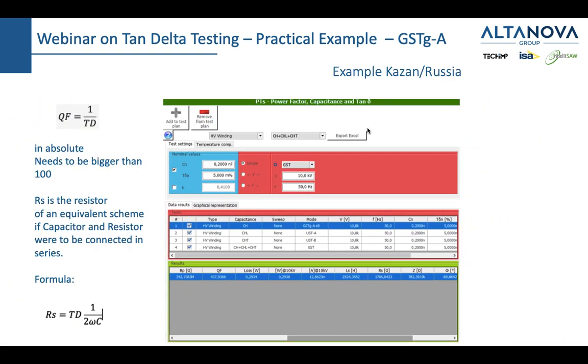The next would be, if 12 kV is the voltage with which the test is done because the insulation is polarized, is there any chance to perform the test on a low voltage side? On a low voltage side, in transformers where the secondary side is less than 10 kV. So, well, when I say 12 kV, I'm saying 12 kV on a transformer which has a nominal voltage more than 12. Of course, if you have 10 kilovolts, you will do a test at 10 kilovolts. And actually, very often people do a test at 10 kilovolts.